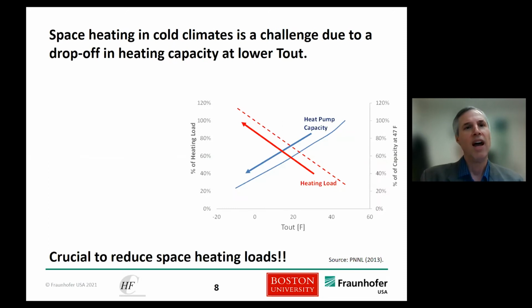Now, what's the challenge with space heating if you go to heat pumps? There's a lot of discussion about going to heat pumps in the sector, and there are packaged rooftop units using electric resistance heating, particularly further south, and in some cases using heat pumps as well. Well, you can see if you look at the outdoor temperatures, it gets colder and colder. The heat pump capacity decreases, but at the same time, the heating load is increasing. And once you start going below this point where they meet, you have to make up this difference somehow. You have to have a supplemental heating system.